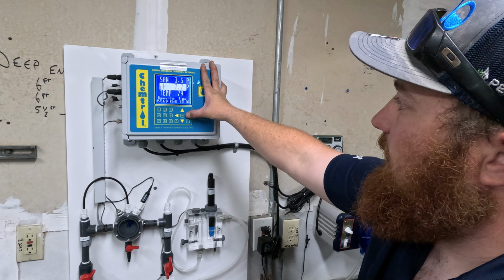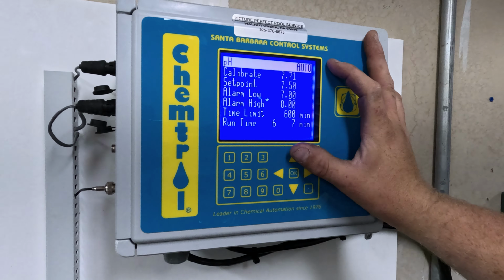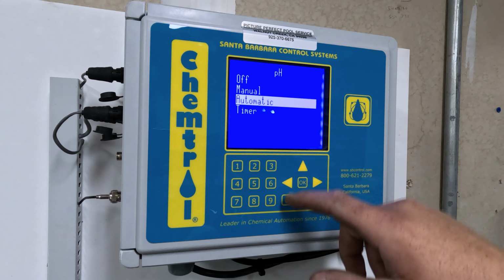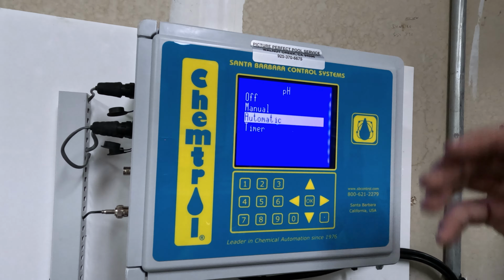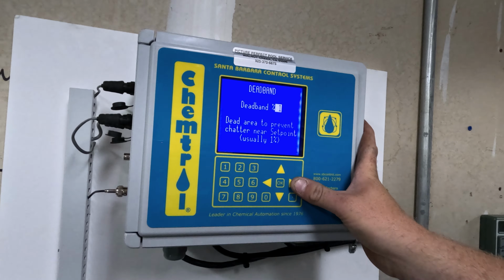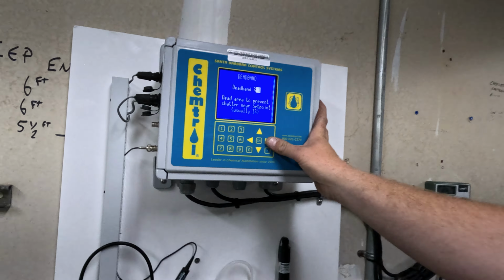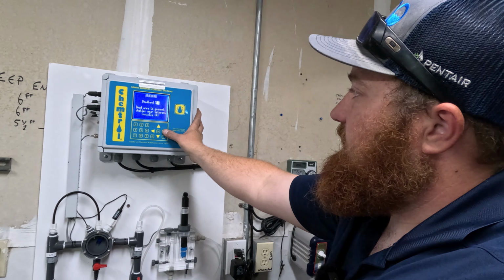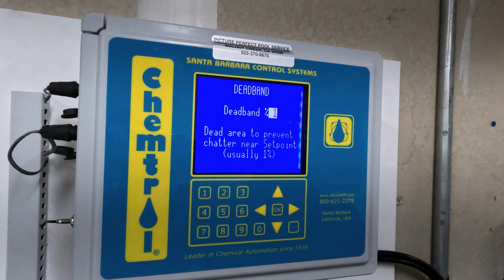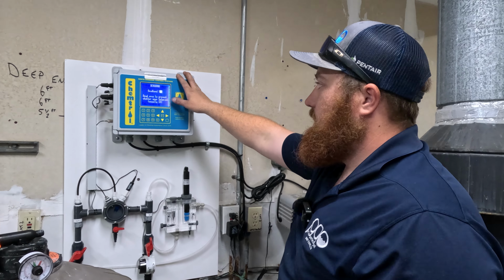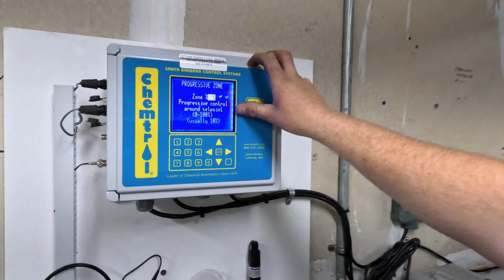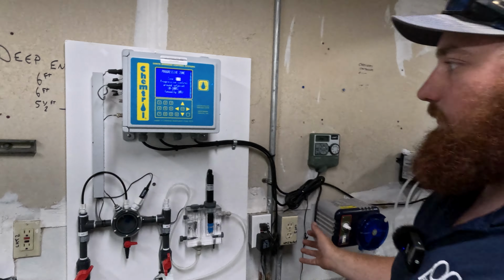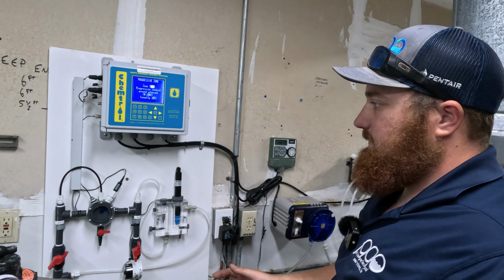So let's go up into our pH menu. Under your pH, it's in auto right now. If you need to manually feed, you go into manual. Under automatic, that's where we want to keep it normally, automatic feed. We want to go into proportional. This is all based off of the size of the body of water as well as the bather demand. The dead band is how far it needs to veer off your set point before it starts to feed. We'll leave it at 1%, hit okay. Progressive zone: the further away your reading goes from the set point, the more it's going to feed. The closer it gets to the set point, it'll turn the feeder pump off, turn it on, turn it off, turn it on, turn it off, and that prevents it from overshooting.